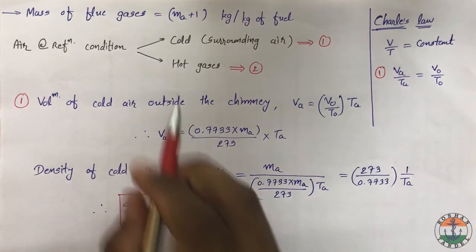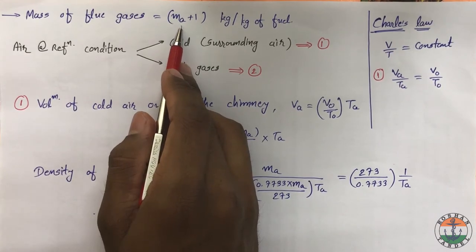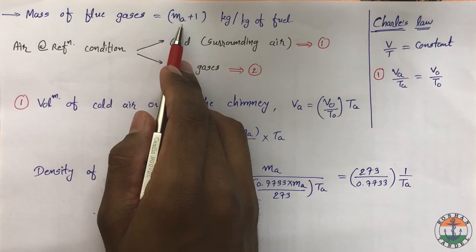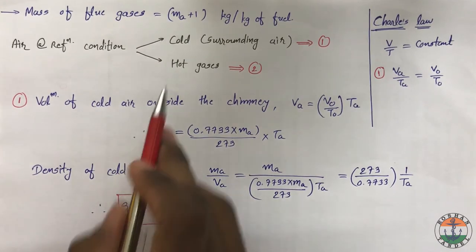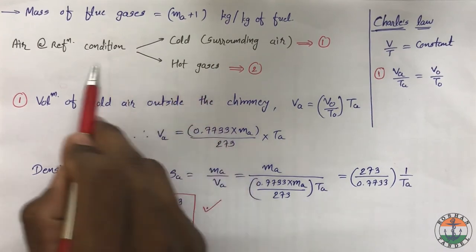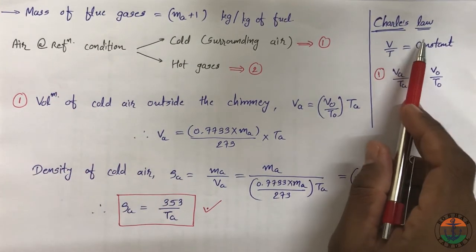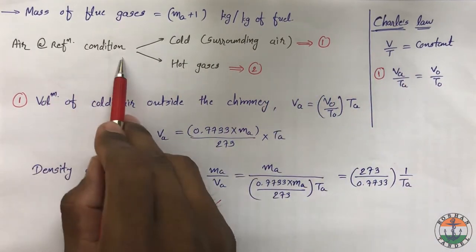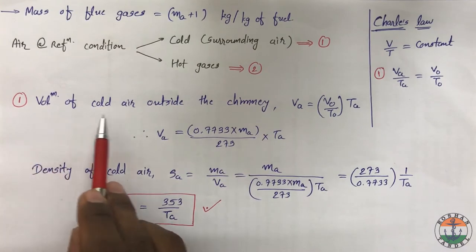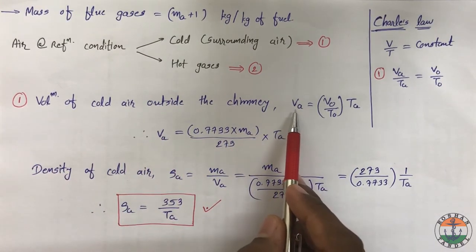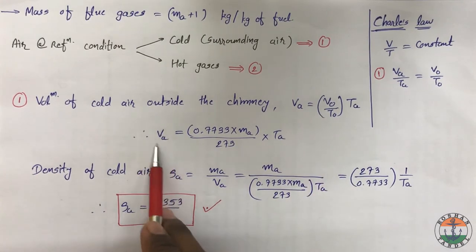Mass of flue gases will be Ma plus 1, where Ma is the mass of air supplied per kg of fuel. For example, supplying 12 kg of air per 1 kg of fuel gives 13 kg of flue gases. Applying Charles' law (V/T = constant) to compare air at reference condition with cold surrounding air, we get volume of cold air outside the chimney VA = (V0/T0) × TA, giving a specific value of VA when V0 and T0 are substituted.